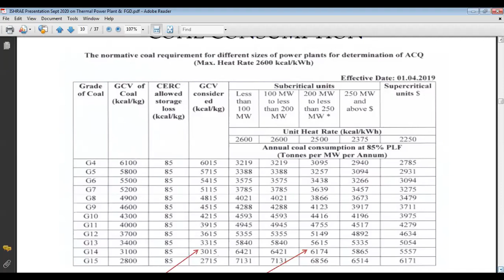You can see for different configuration of power station, the heat rate is given. Like for unit capacity less than 100 megawatt, the station heat rate is 2600. 100 to 200 megawatt, it is again 2600. But 200 to 250, it is 2500. For 250 megawatt and above, it is 2375. And for supercritical thermal power station, it is 2250. So this is the station heat rate.